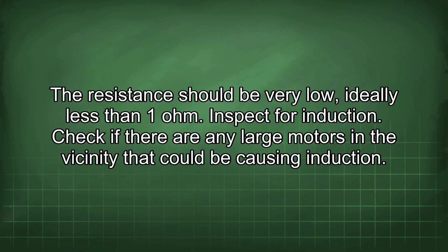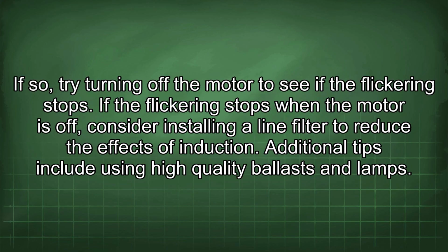Inspect for induction. Check if there are any large motors in the vicinity that could be causing induction. If so, try turning off the motor to see if the flickering stops. If the flickering stops when the motor is off, consider installing a line filter to reduce the effects of induction.